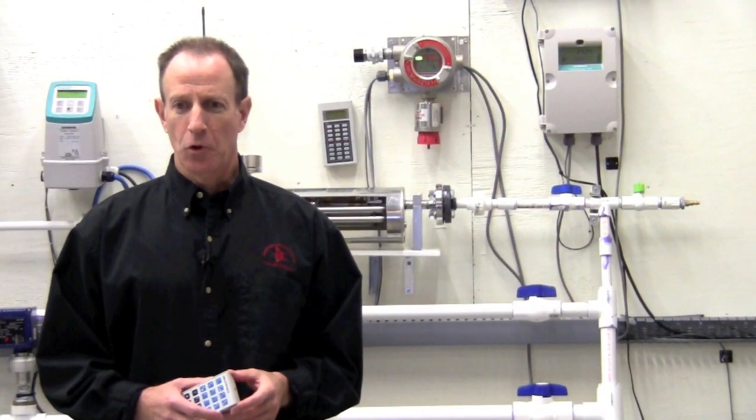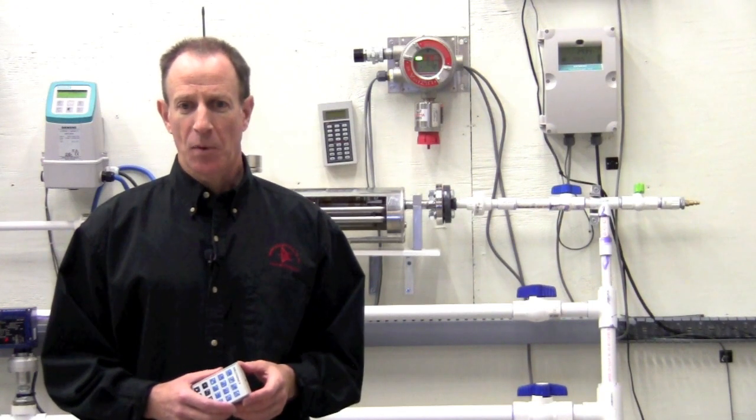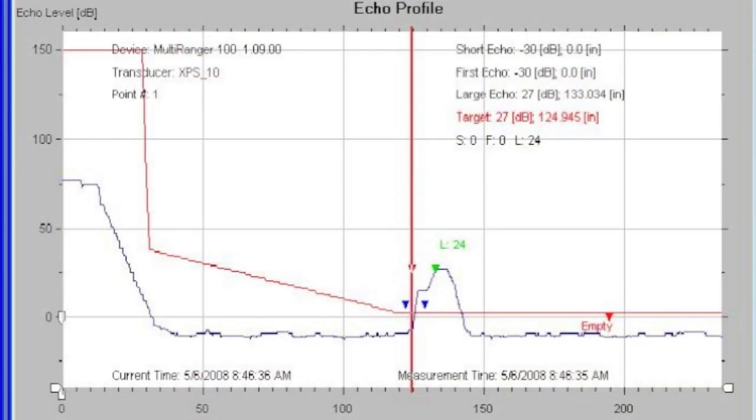By connecting the MultiRanger to a PC running Siemens PDM software or Dolphin software, we can take a look at the complete echo profile. This can tell us where, if any, false echoes are being reported.